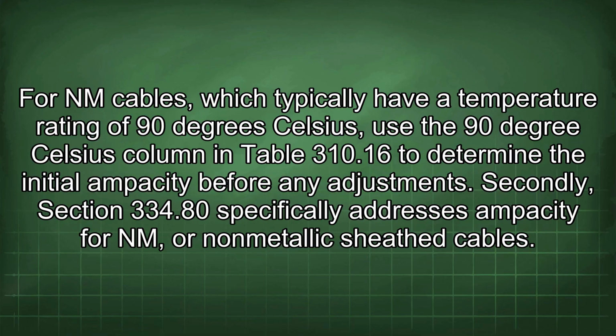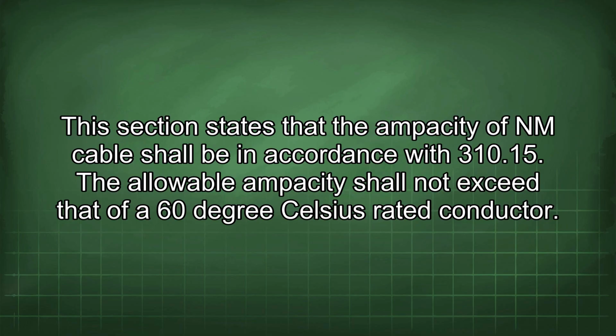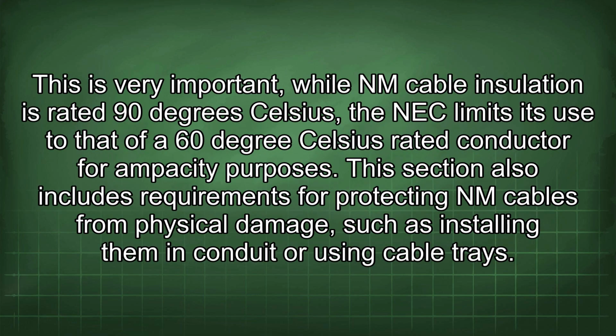Secondly, Section 334.80 specifically addresses ampacity for NM, or non-metallic sheath cables. This section states that the ampacity of NM cable shall be in accordance with 310.15. The allowable ampacity shall not exceed that of a 60 degrees Celsius rated conductor. This is very important. While NM cable insulation is rated 90 degrees Celsius, the NEC limits its use to that of a 60 degrees Celsius rated conductor for ampacity purposes.